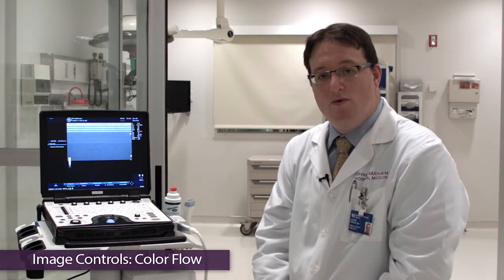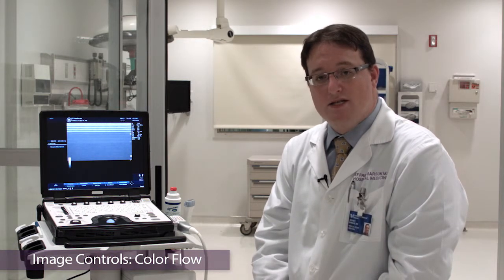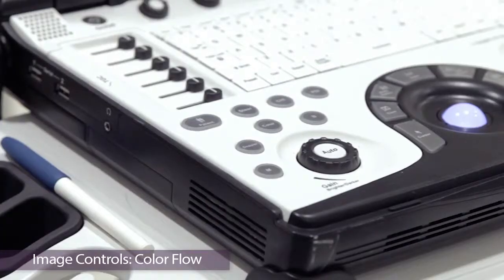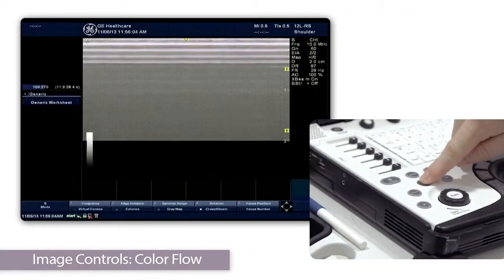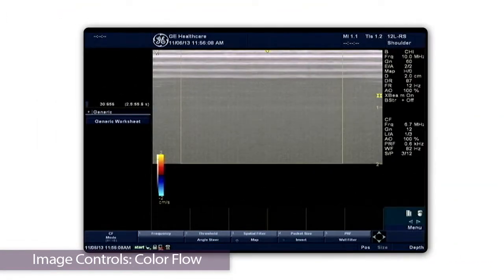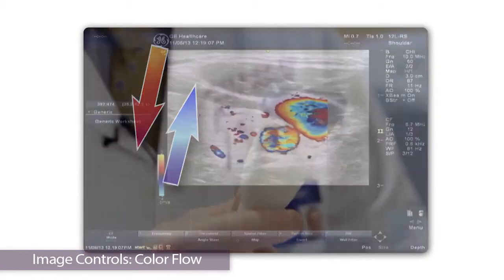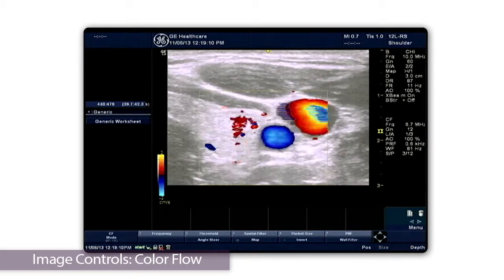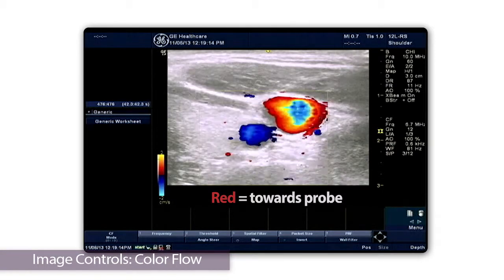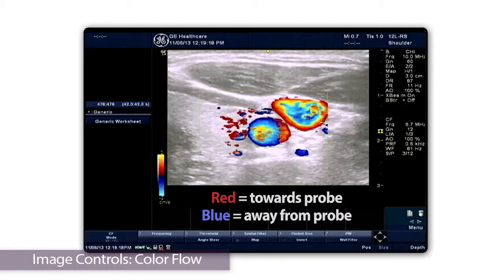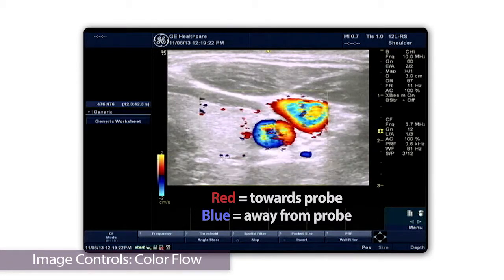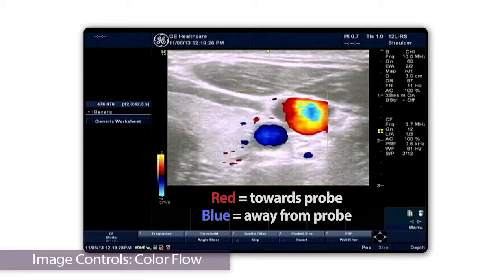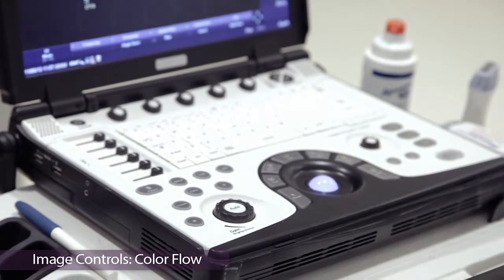The final concept that we need to discuss is color flow. As you can imagine, we will be looking at arteries and veins with our vascular probe, and sometimes it can be difficult to distinguish the two. The color flow button is right here on the GE machine. When I push this button, what you'll notice is a color screen comes on, red and blue, and you'll see a box. Within this box, you can evaluate the flow of the vessel. Directionality of the probe is what detects the color difference. So, if the blood flow is coming towards the probe, the color will be red on the screen, and if the blood is going away from the probe, the color will be blue. Therefore, how one orients the probe can distinguish between arterial flow and venous blood flow. To turn the color flow off, all you have to do is push the color button again.